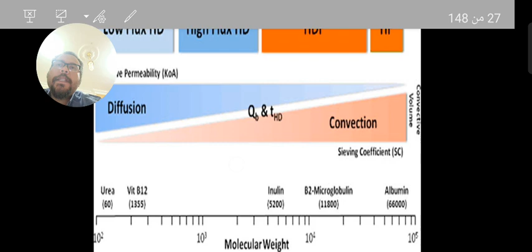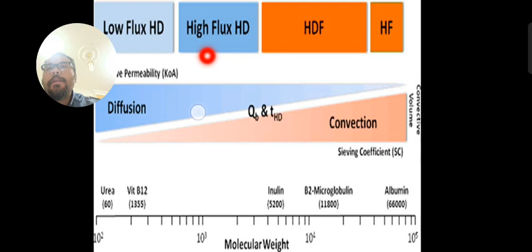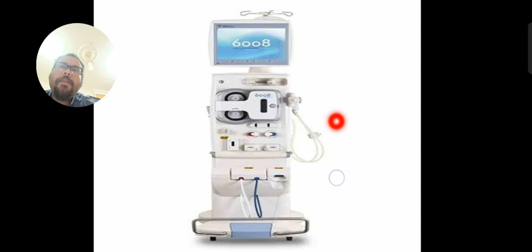The second point, we must know the types of dialysis we need. We have low flux hemodialysis, high flux hemodialysis, HDF hemodialysis and HF hemodialysis. Mainly in Egypt and in our unit, we use high flux hemodialysis. HDF is used in less than 5% of cases in Egypt. HDF uses high flux hemodialysis and is done by this machine. In our unit we have only 3 machines for HDF.